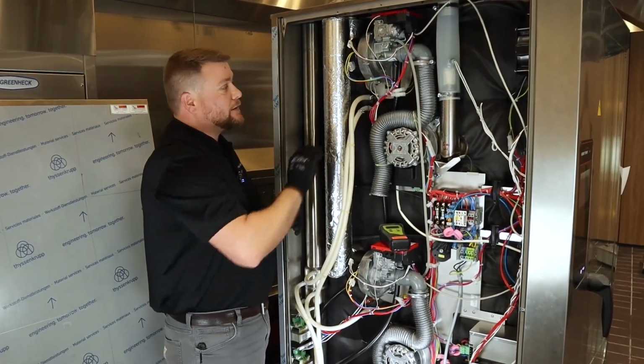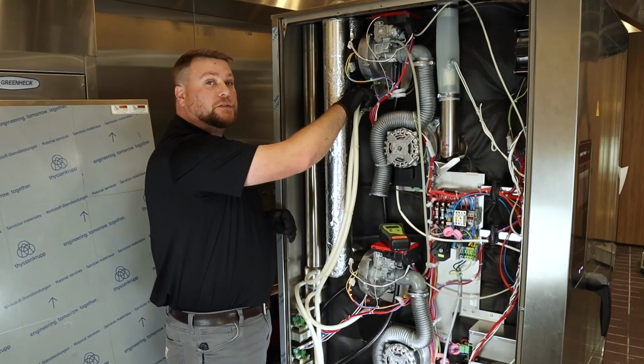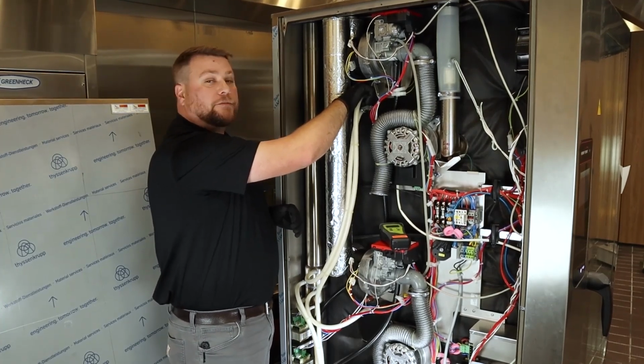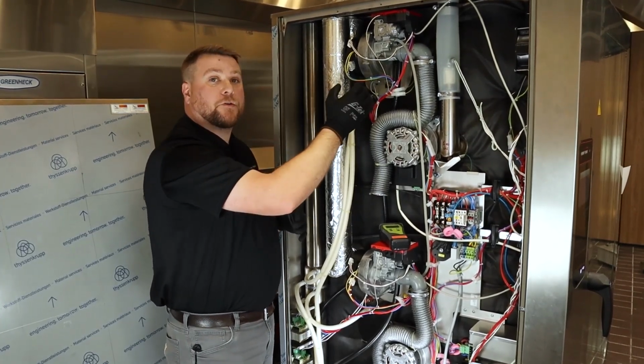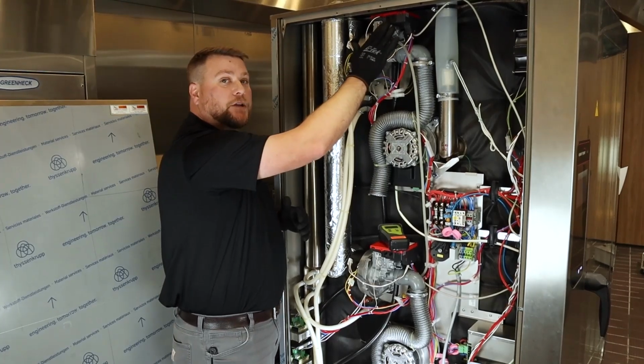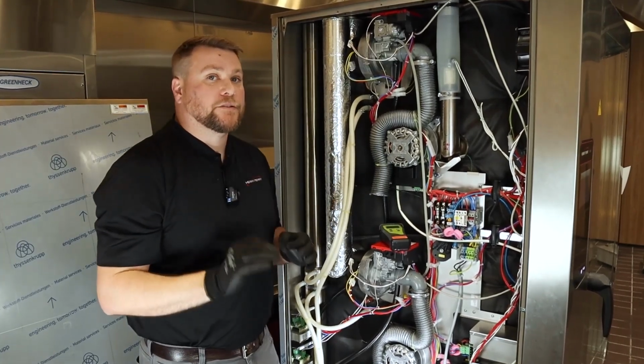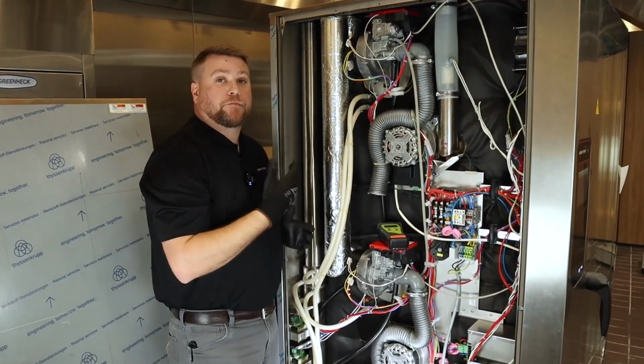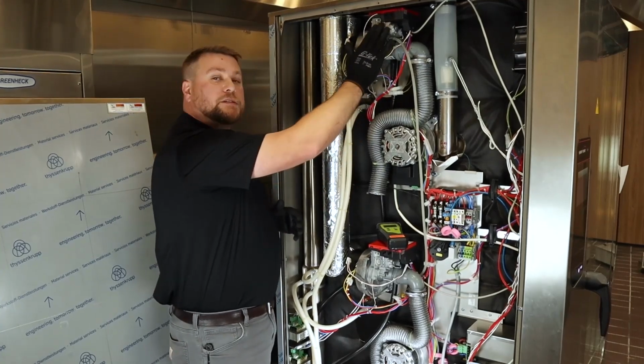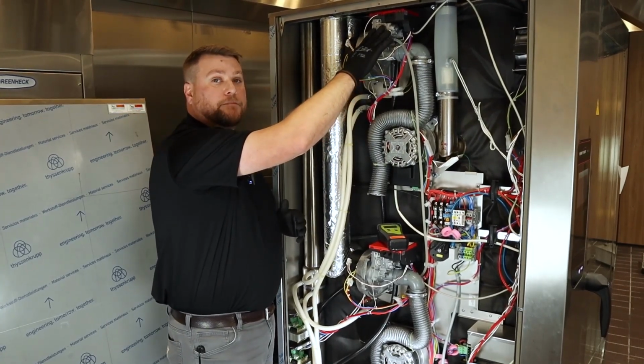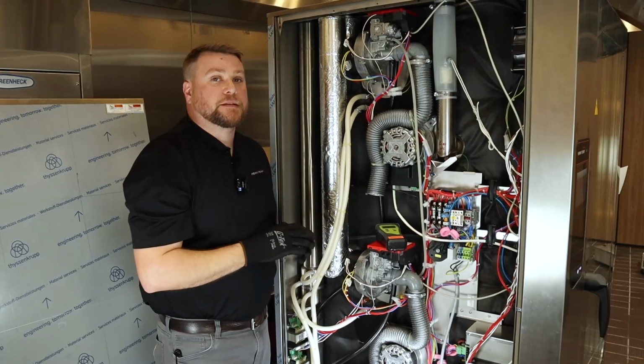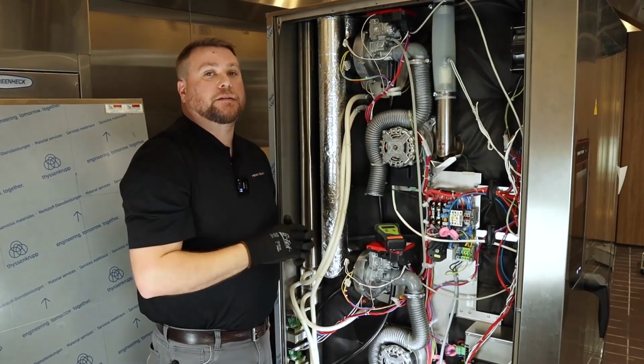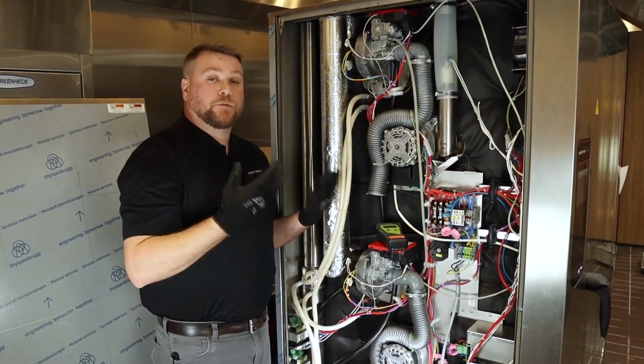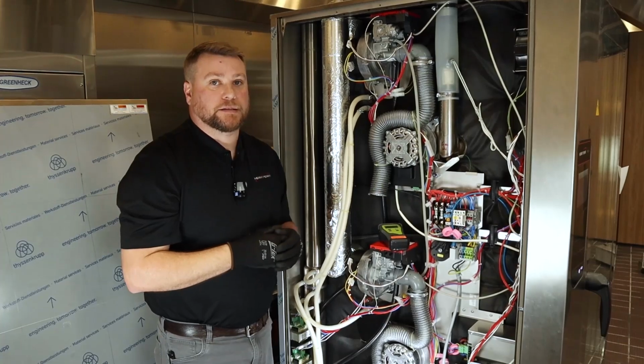Now, after we get that ignition, that's where our flame sensor is going to come into play, and our flame sensor is going to deliver that microamp reading back to our ignition module. Now, keep in mind, we need at least 3 microamps there to have proper flame sense. And then once the ignition module receives that 3 microamps for flame sense, that'll deliver that back to the control board, and then it will be a complete ignition process.